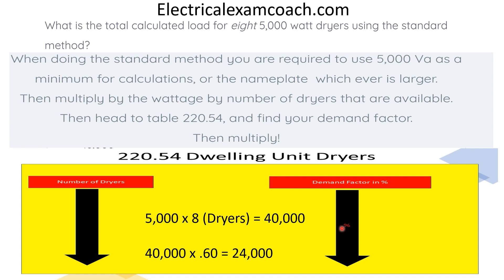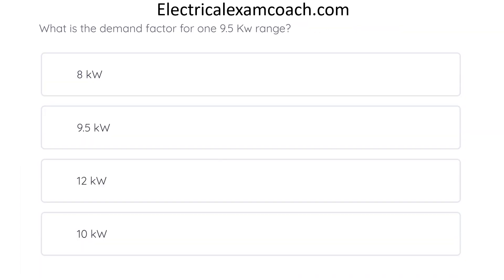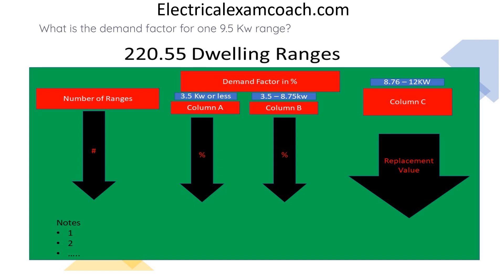I am the Electrical Code Coach, and you can head to electricalexamcoach.com to learn about more topics like these. What is the demand factor for one 9.5 kW range? The correct answer is 8 kW. To find this, we head to Table 220.55. The first question we always ask is: what column does our range fall in? Ours is a 9.5 kW range, so it falls into Column C. We start on the left-hand side of the table, find our number of ranges — which is 1 — and tee off with the Column C value, which is 8 kW. We have to remember that Column C is not a demand factor, but rather a replacement value.